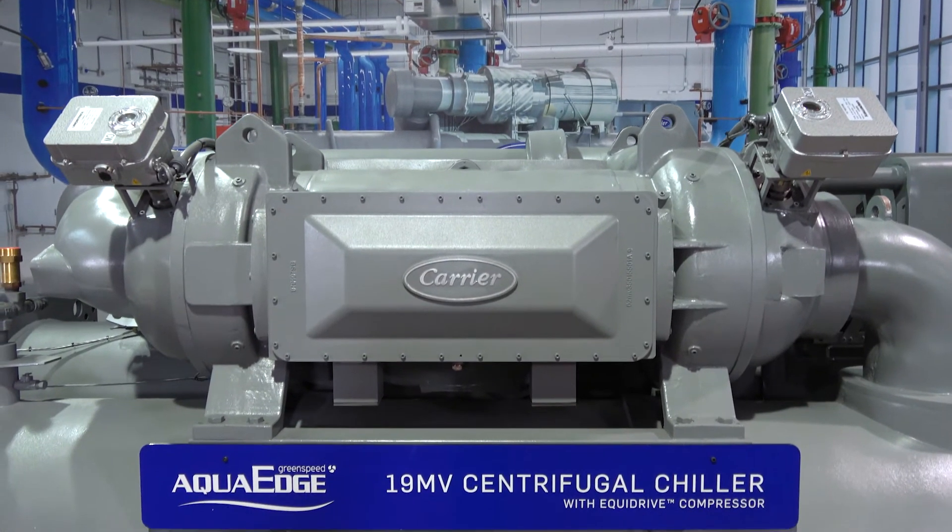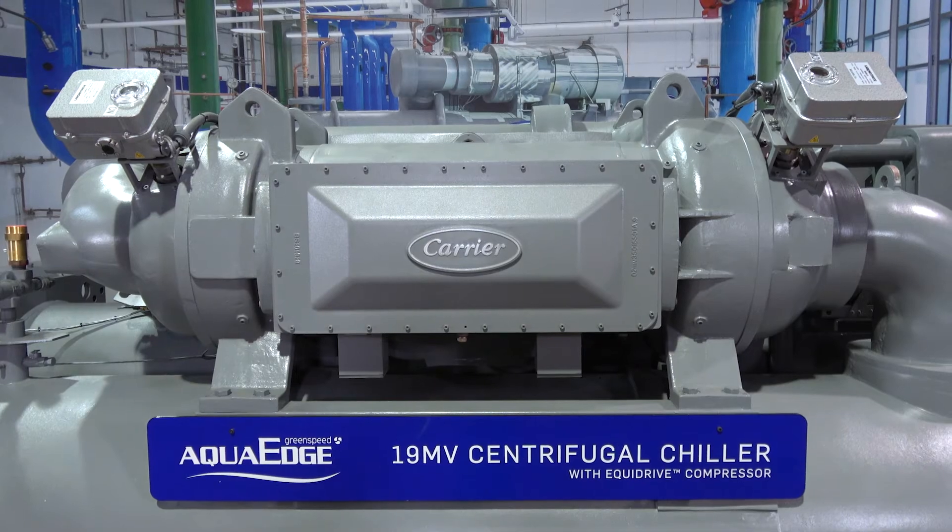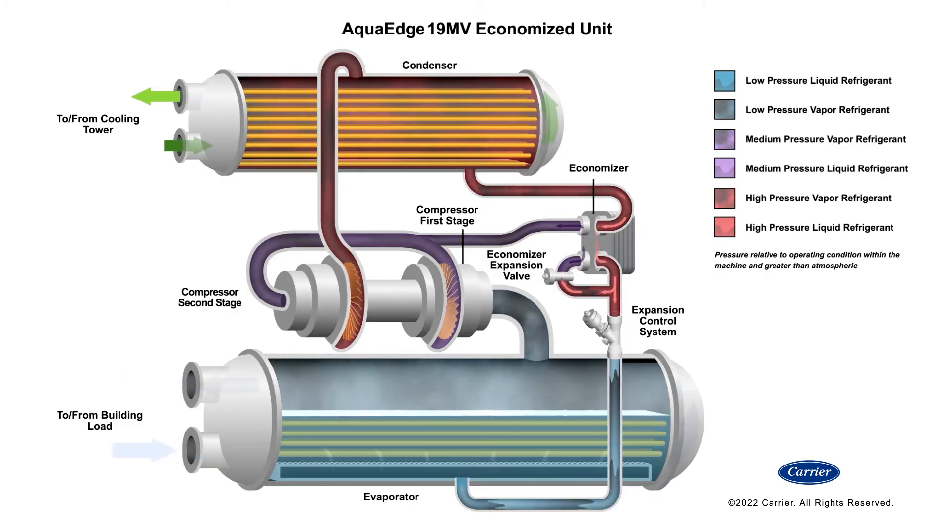The Equidrive compressor features an optional refrigerant side brazed plate economizer. If you've ever done building modeling analysis, you may have noticed that a bulk of your ton hours occur in and around the 75% load point. The economizer leverages the two-stage design to make sure the 19MV is as efficient as possible where you run chillers the most.